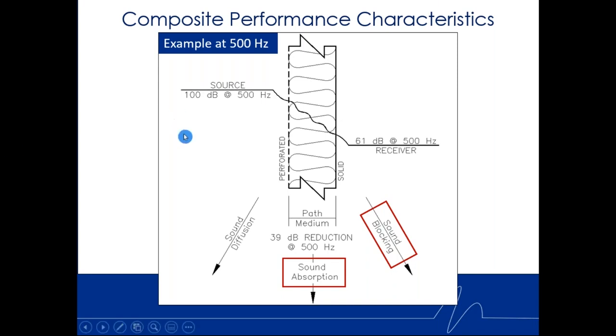And if I gave you an example here, we looked at just the 500 hertz center frequency, say, and we have a noise source, maybe a fan inside a built-up air handling unit. The fan is generating a 100 decibel sound power level at 500 hertz. That sound energy is going to propagate through the perforated inner shell of the panel. We show the perforated inner shell here. As that energy propagates into the acoustic media, some of that sound energy is going to get absorbed and reduced. And before it can even impinge on or try to propagate through this solid surface of the outer shell of the panel, that noise energy of 100 dB has already been reduced some.